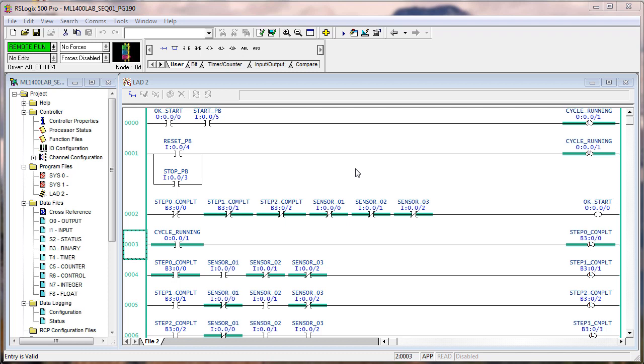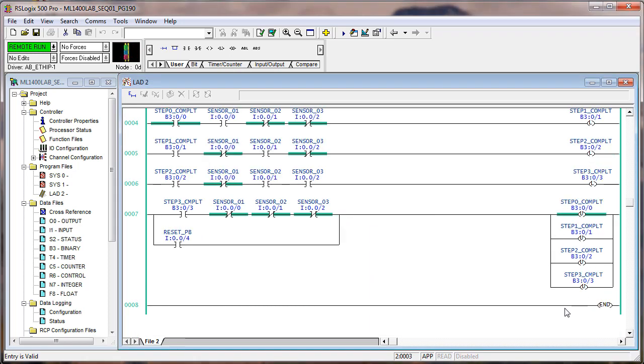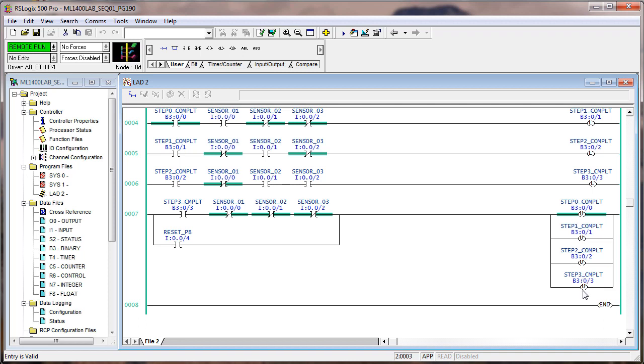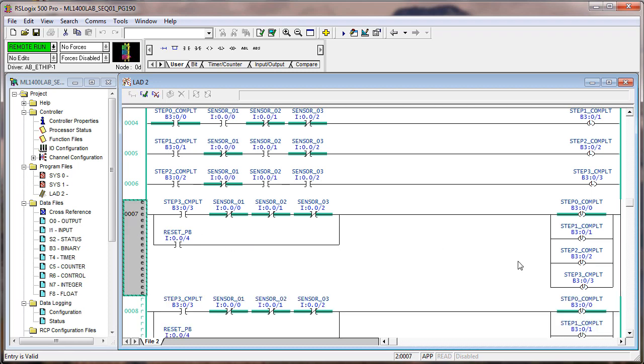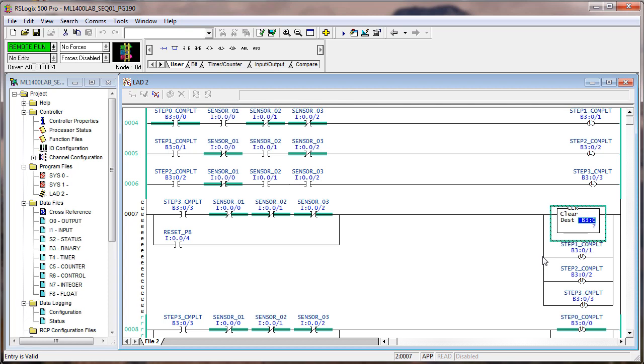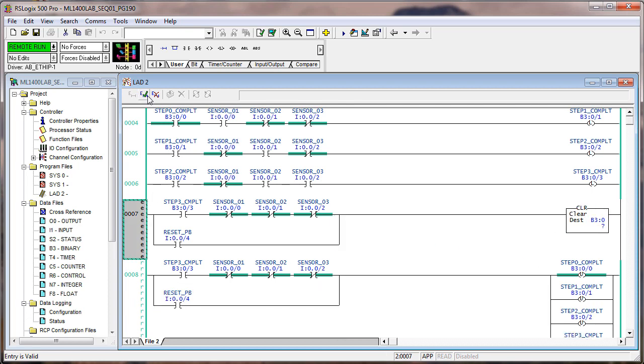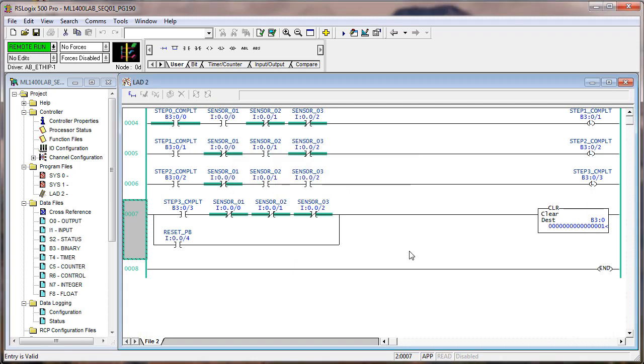These are just little small steps. And we keep adding logic to make our sequence logic more complete. Now instead of using this fat rung here, I mean we've only got four steps here: zero, one, two, and three. Well, let's say we had 12 steps. Putting 12 of these in parallel, that makes for ugly looking code. So instead, because we were smart enough to put all of our step completes in B3 word zero, we can simply replace this with a clear B3 zero. Delete these rungs or branch arounds. And it serves the exact same purpose.